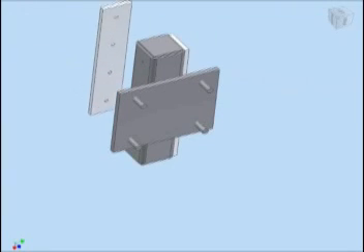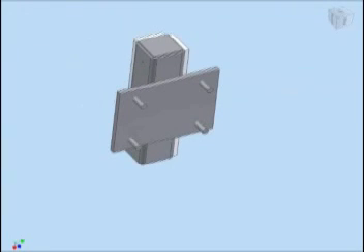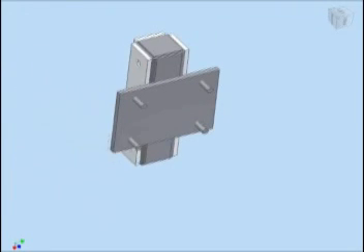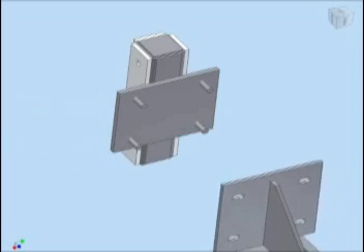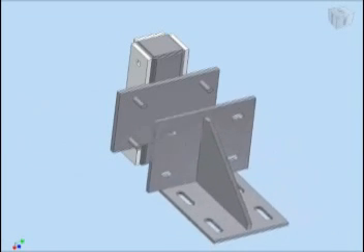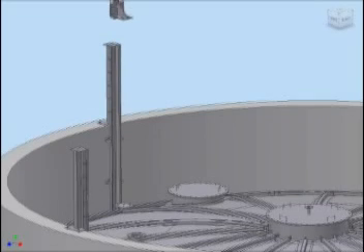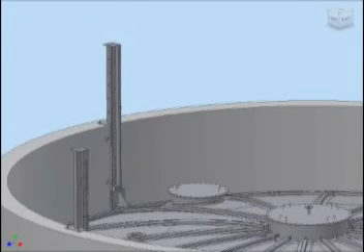Install slide brackets and slide bracket adapters. The slide brackets should be adjusted radially so that a quarter inch gap exists between the UHMW slide plates and the slide guide plate. Slide bracket assemblies should track approximately in the middle of the slide guides. The installation is now complete and the cover is ready for testing.